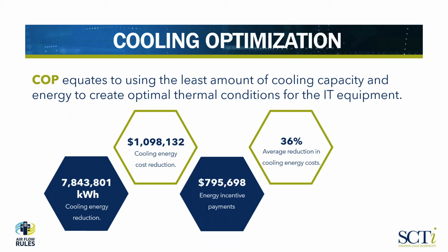On average, across all of the sites we've done over the last 3 years or so, cooling energy reduction has been on average 36%. When we look at the cost of a data center operation, as I noted earlier, cooling can represent between 30 to 60%. If we take a number, let's say 40%, we're looking at about a 15 to 20% reduction in overall operating costs for a data center.